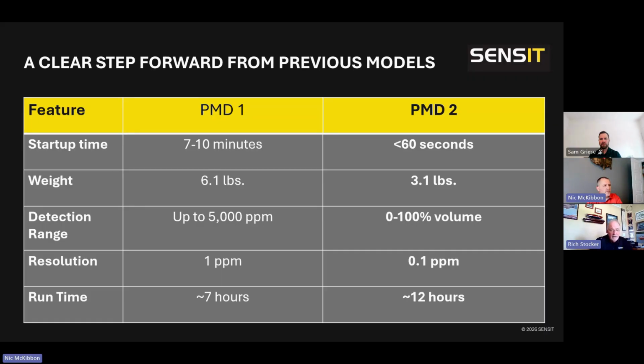Weight is a huge advantage. The laser array built into the unit is very lightweight and works fantastic. Our detection range takes us from no gas all the way up to 100% by volume, so we're not having to switch back and forth between instruments. Our low level resolution, as I mentioned before, is a 1/10 of a part per million, and we publish 12 hours of runtime on a battery.